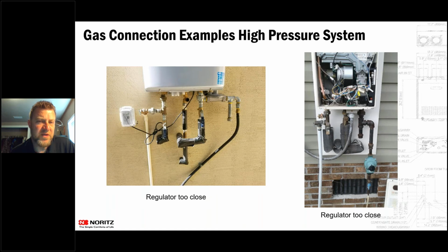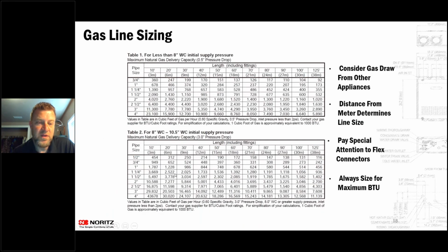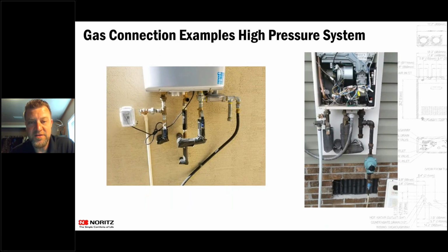Yeah, so in our EZ111, 199,000 BTUs, our book says half-inch line up to 30 feet, but that's using the National Fuel Gas Code 3-inch drop chart, which is this chart right here, where a half-inch gas line at 30 feet says 250,000 BTUs. A lot of places around the United States use a half-inch pressure drop. So with that half-inch pressure drop at 30 feet, I'm still at 3/4. I'm 100. But there are a lot of places that do have this 3-inch pressure drop, where that half-inch line at 30 feet, 250,000 BTUs, has worked just fine. But that's only with the tankless water heater on your gas supply and nothing else. There are a lot of fine details to it. I always err on the side of caution and make sure you have enough gas there no matter what.